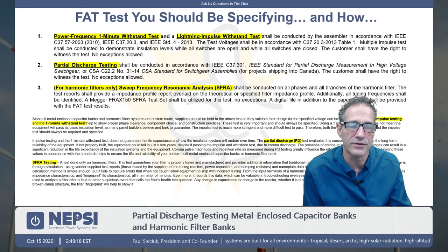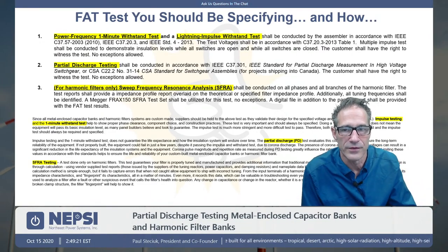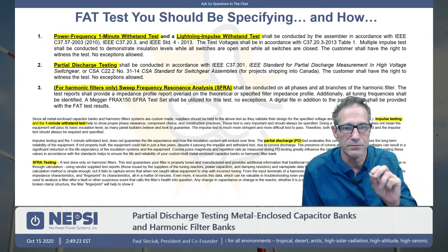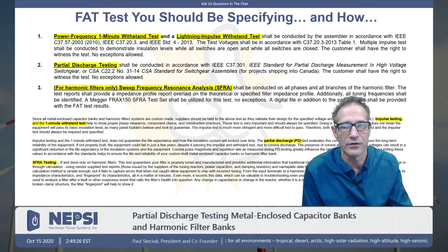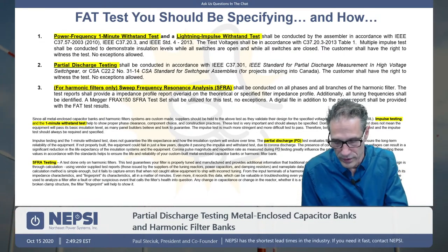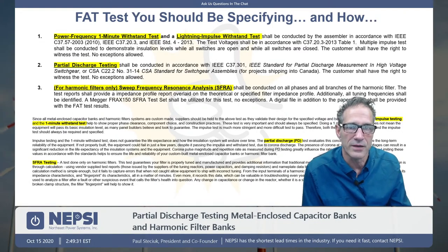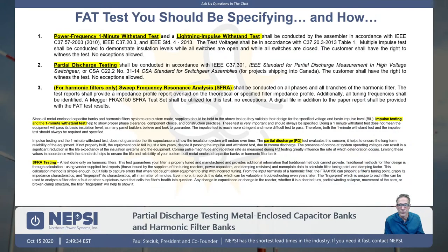And SFRA testing is about making sure that your filter actually has the impedance profile that you asked for. And those are the three tests that we really think should be specified on metal enclosed cap banks and filter banks. So if you're specifying this type of equipment, these are the lines to add to your specification. So if you're creating a specification, come to our tech talk and you can specify those. Our guide form specification is located on our website and also contains all these test requirements and some other additional tests that we recommend to make sure that you're getting what you asked for.